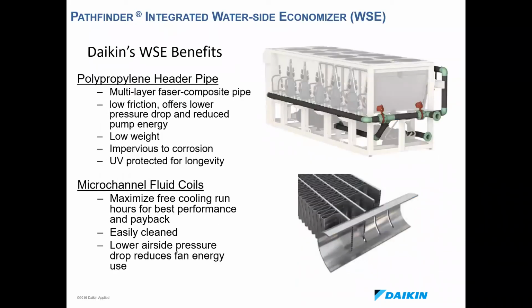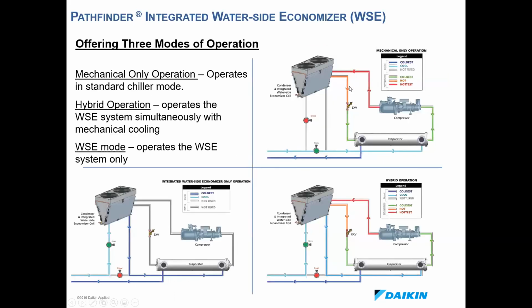Here's a little bit on the IWSE. This is a new option from us. It's an integrated water side economizer that you can use to leverage your ambient temperatures to offset your mechanical cooling load. We use a polypropylene pipe. Our competitors still are using metal in some scenarios, which helps us out a lot because the polypropylene has lower friction, a lower pressure drop, and reduced pump energy because of that. It's also very low weight. It doesn't corrode and it's UV rated. And the IWSE coils are going to be the same microchannel coils that we use for the refrigerant as well. They'll just be right up against it.